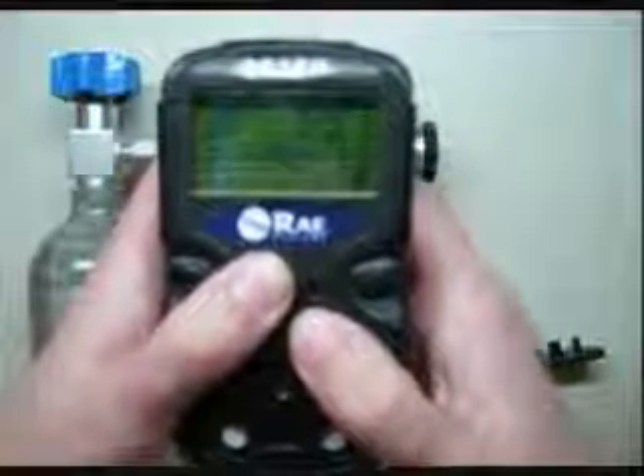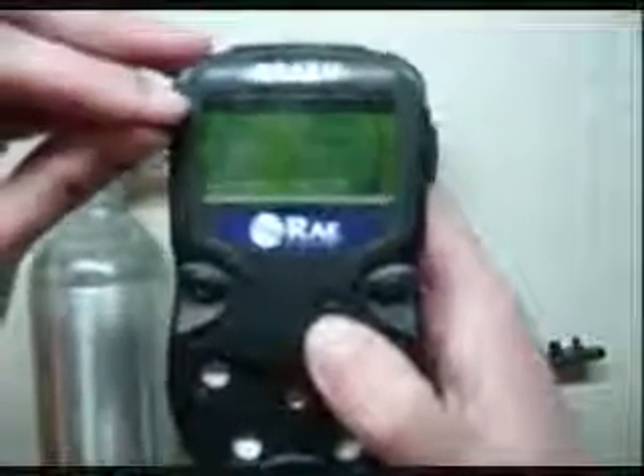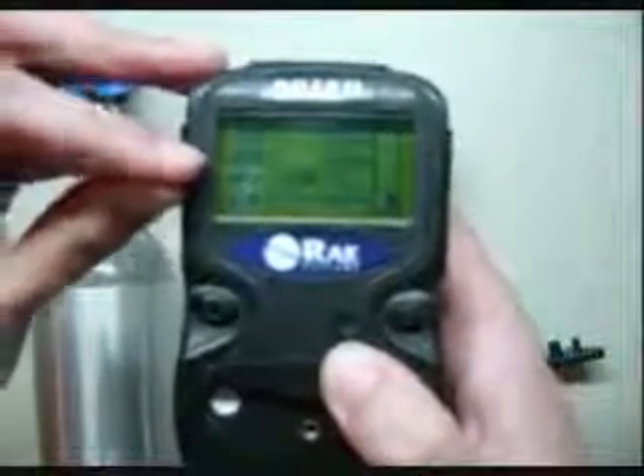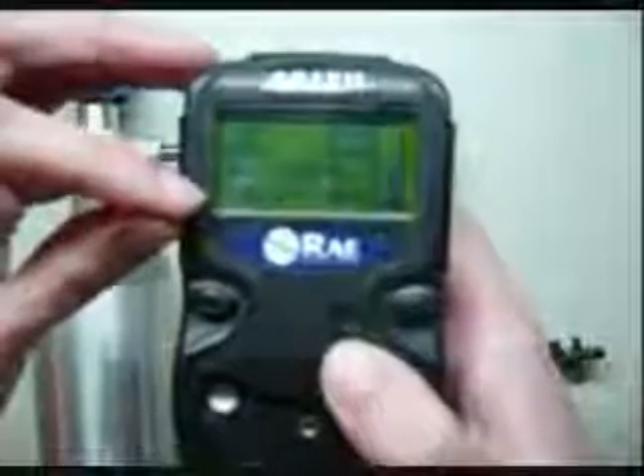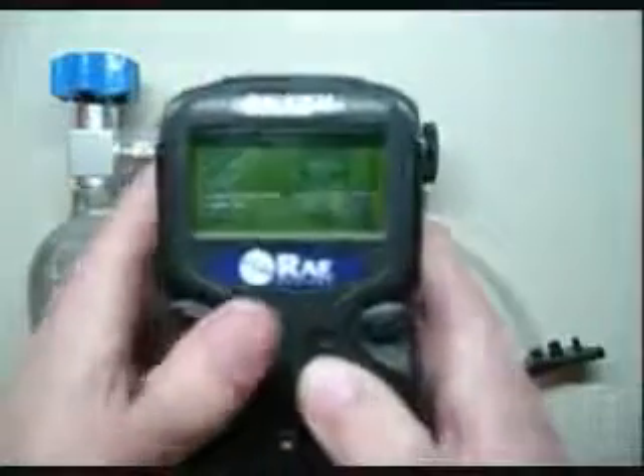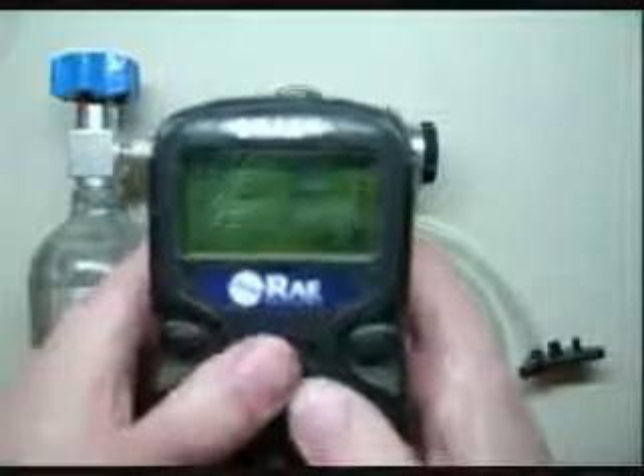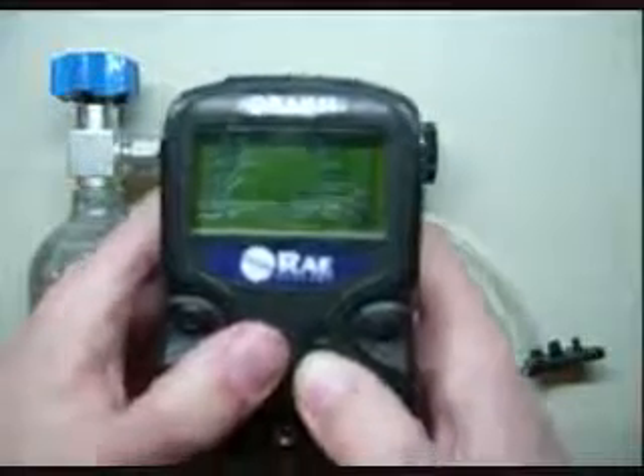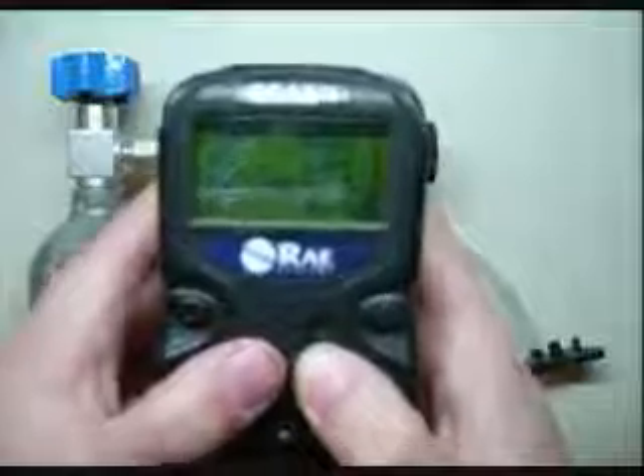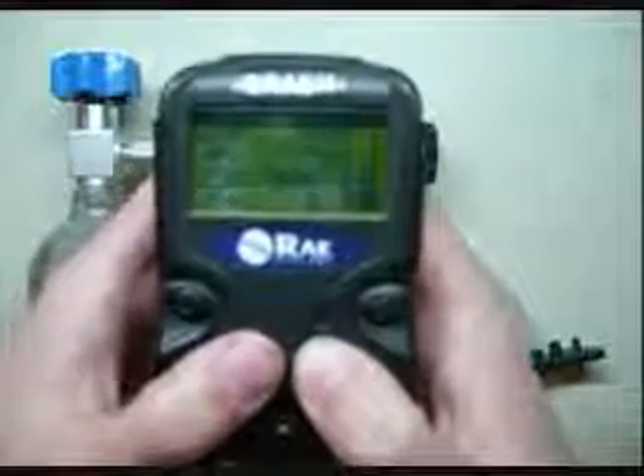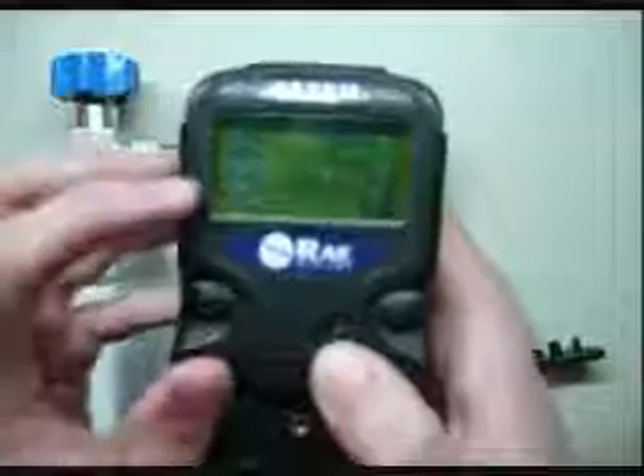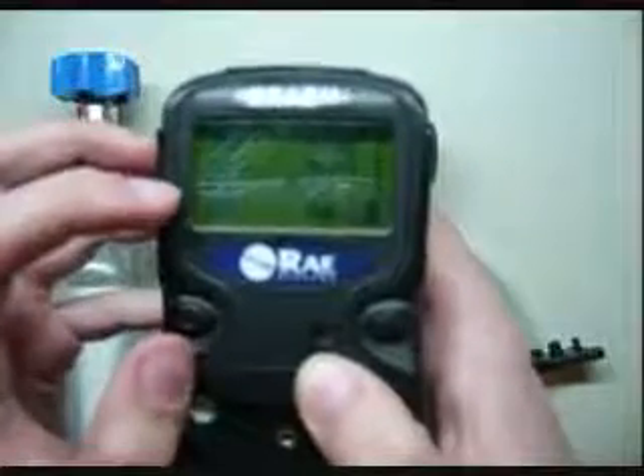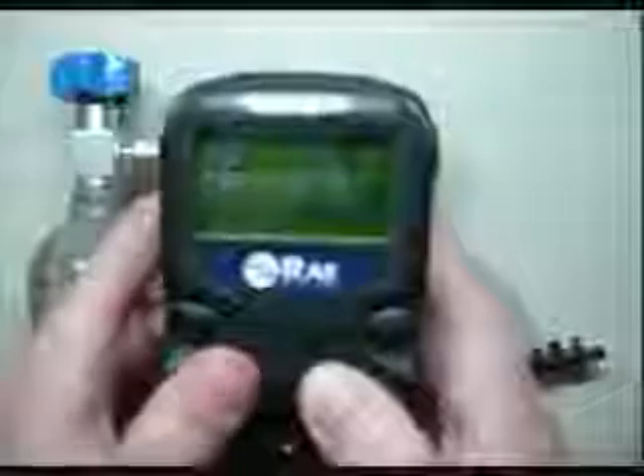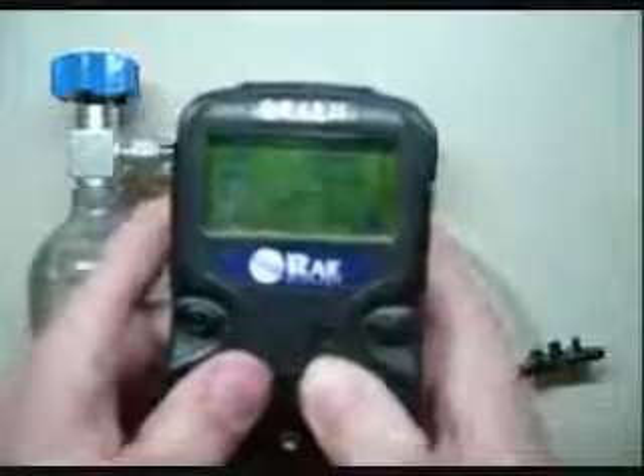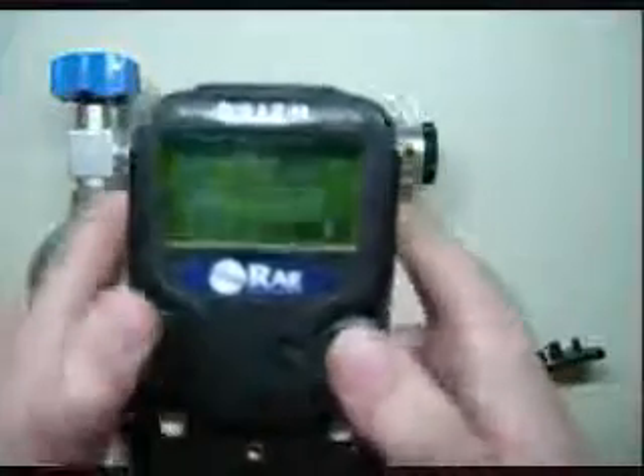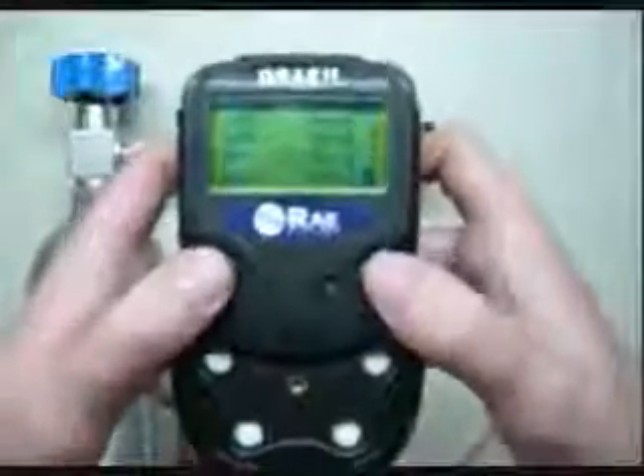And here we go. It gives a beep for us, and we can see that there's the CO sensor at the top, H2S, oxygen, and your LEL at the bottom. This one's looking for methane. The calibration gas you're going to be using today is 50 parts per million carbon monoxide, 10 parts per million hydrogen sulfide, 18% oxygen, and 50% LEL methane. And normally the oxygen doesn't matter what percentage you have, you just use it for a bump test. But on the QRAE units, a lot of times they'll actually calibrate to whatever oxygen you have, so the 18% oxygen is important here.